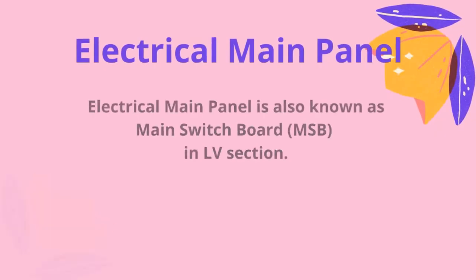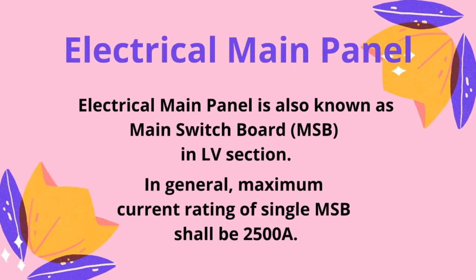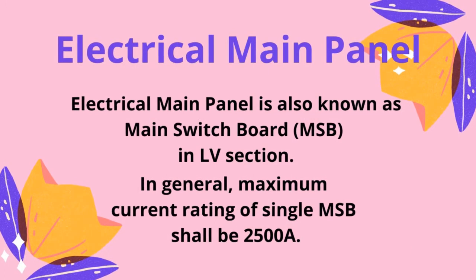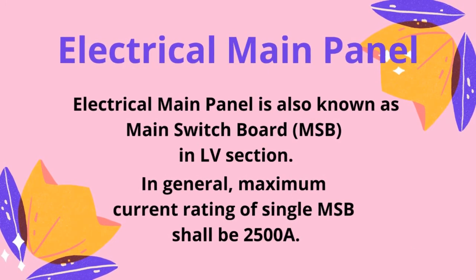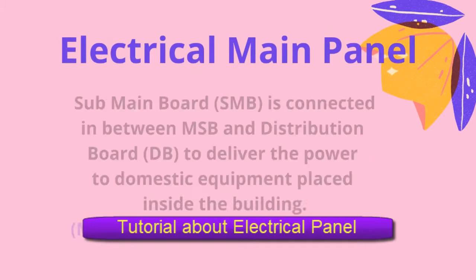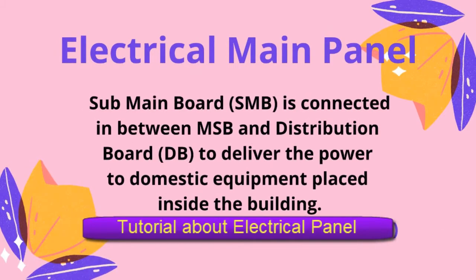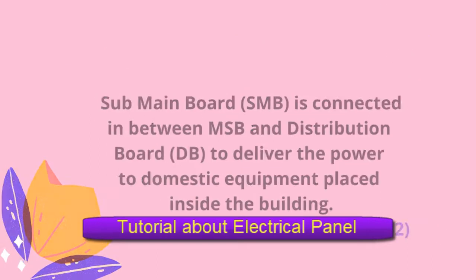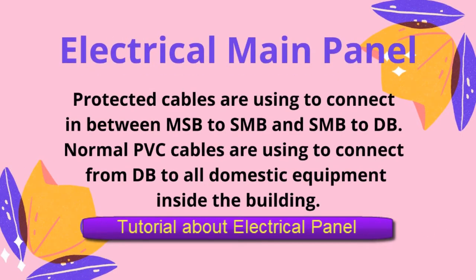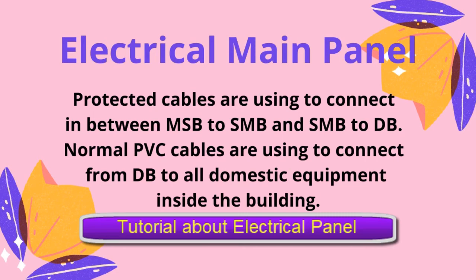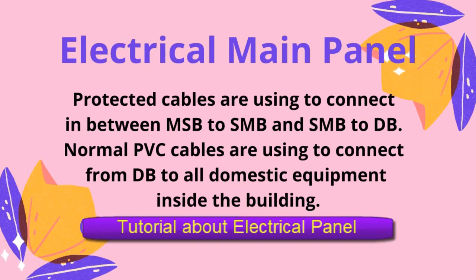The electrical main panel is known as the main switchboard in the LV section. In general, the maximum current rating of a single MSB shall be 2500A. The sub-main board is connected between the MSB and the distribution board to deliver power to domestic equipment inside the building. Protected cables are used to connect between MSB and SMB, and SMB to DB. Normal PVC cables are used to connect from DB to all domestic equipment inside the building.